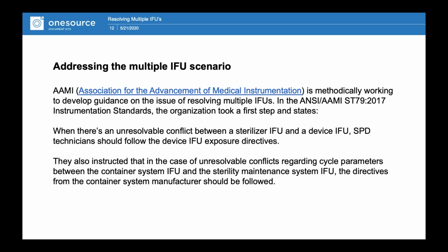We could have a separate webinar on that alone, but don't ever confuse your sterilization or terminal sterilization with dry time. The dry time is important because on certain devices, we have to make sure that they are dry. Wetness post-cycle, a wet pack, can indicate contamination. We have to assume that the device is contaminated unless it's in a device that's approved for that. And it's not just the one tray. There are some IUSS devices you can use, like a Riley flash pack, where there's moisture. I believe Steris and Case Medical have devices that are similar to that. Wetness inside the container does not always necessarily mean it's contaminated if the IFU indicates that.